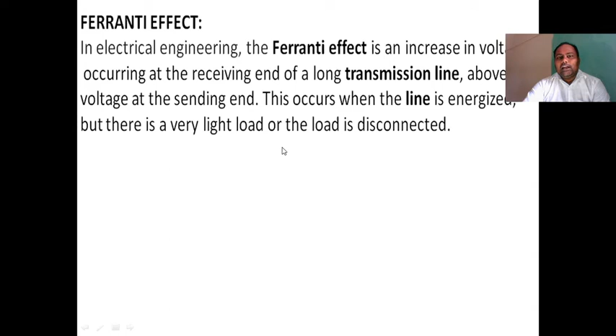So in which case is VR greater than VS? In lightly loaded or no load condition, VR is greater than VS. How is this possible? It is possible only due to the capacitance effect. In electrical engineering, the Ferranti effect is an increase in voltage occurring at the receiving end of a long transmission line above the voltage at the sending end, i.e. VR greater than VS. This occurs when the line is energized but there is very light load, or the load is disconnected, under no load or lightly loaded condition.